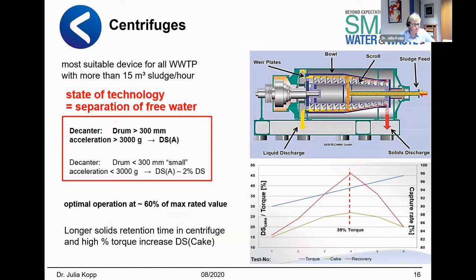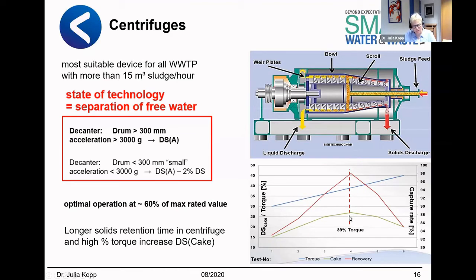Most common are also centrifuges. The incoming sludge is conditioned inside the pipe, thrown out onto the bowl, transported by the screw, and the water flows out. The operation of the centrifuge is related to the torque — the power needed to bring the sludge out of the bowl. With increasing torque you get better dewatering results up to a certain point. Afterward, the shear stresses are so high that all flocks are destroyed, the capture rate goes down, and the cake too. State of technology: if you have a large centrifuge — more than 15 cubic meters per hour — you can release all free water, and operate optimally at about 60% of max rated value.